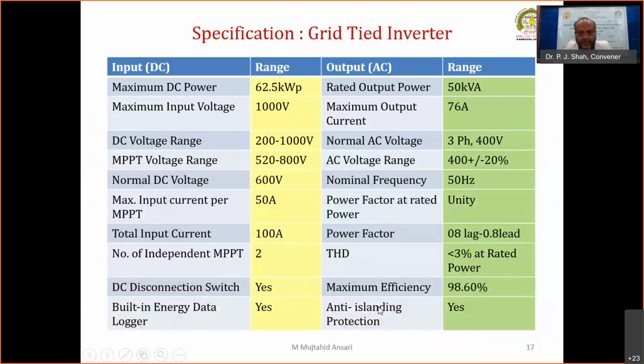switch under maintenance work, and it is necessary for MSDCL. Otherwise, MSDCL does not give permission to connect a solar plant to the grid system. No doubt, our inverters have anti-islanding protection; the flag is yes. Even so, because it is inbuilt in the inverter and not visible, it is necessary to put one more islanding switch in the generation panel from the protection point of view. I will show a picture of this islanding switch also.